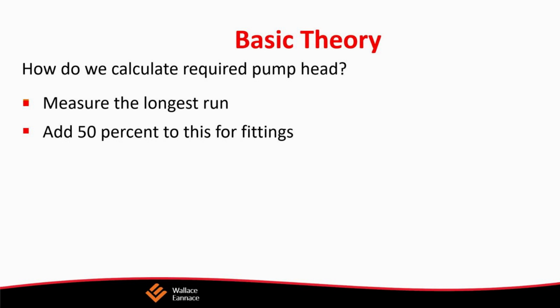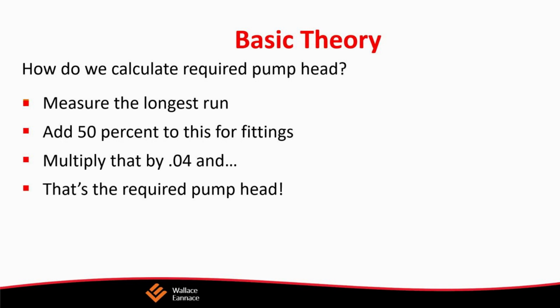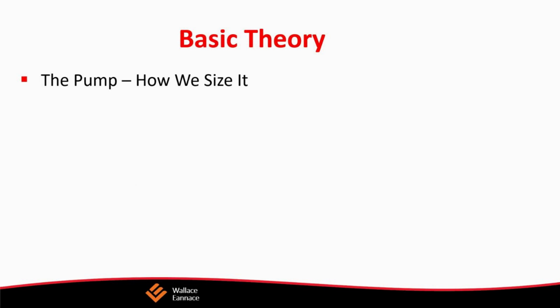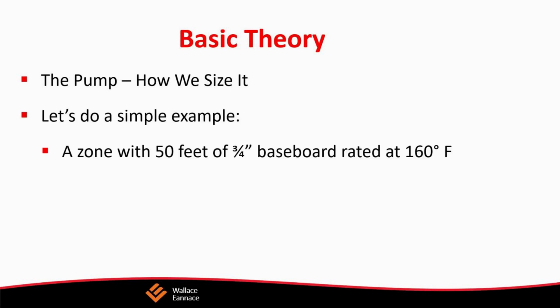So how do we size a pump? Well, there are two main considerations. How many BTUs is a pump going to deliver? And from that information, we'll know what the GPM is, or the flow rate will be. And then how much resistance will the pump have to overcome to get the water where it needs to go?